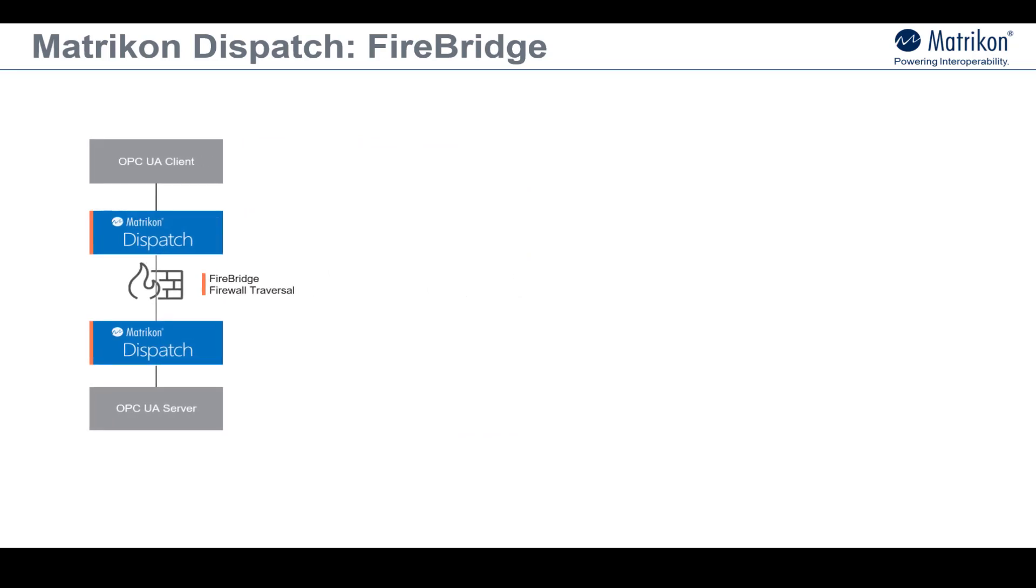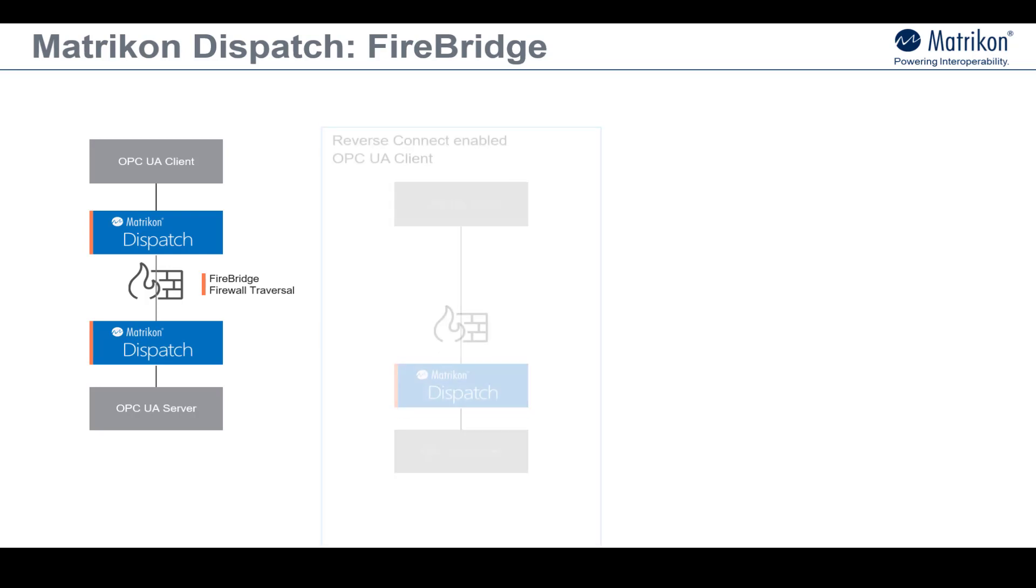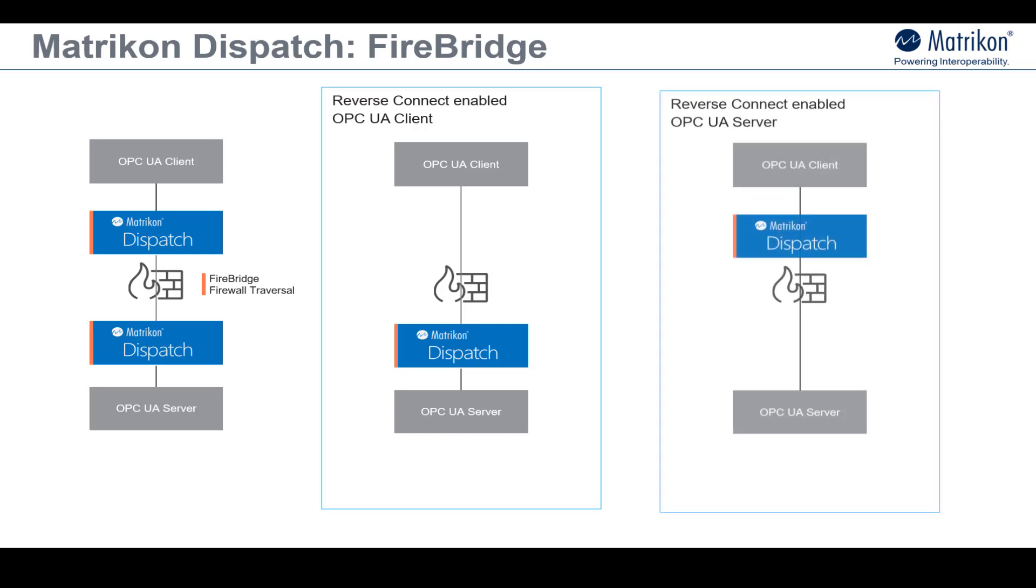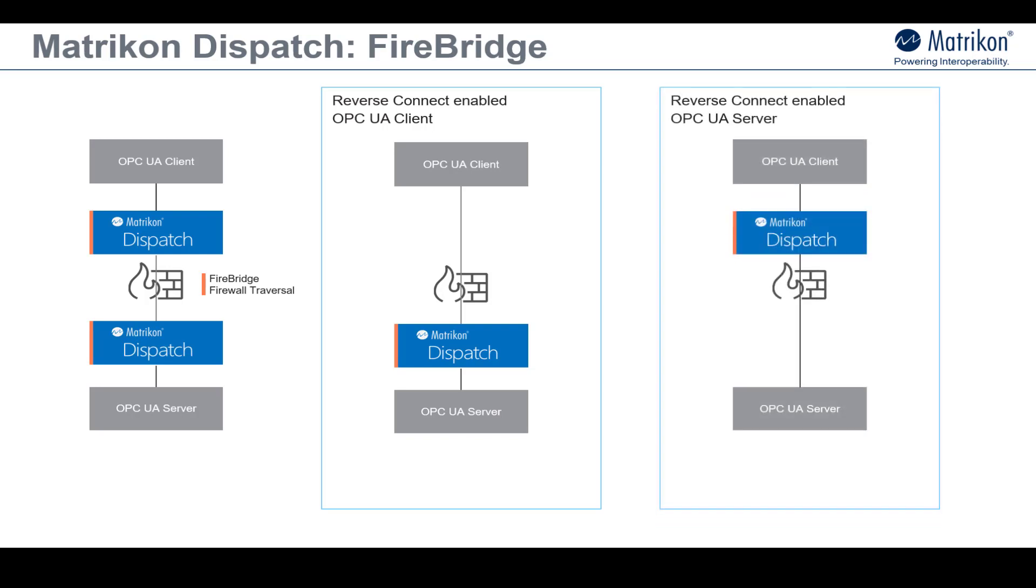As such, Matrikon Dispatch FireBridge technology can be used to facilitate cross-firewall communications on both sides of a firewall in scenarios where neither of your OPC UA clients and servers implement reverse connect functionality. Or, Firebridge can be used to fill in the reverse connect functionality in situations where one of your OPC UA components already supports reverse connect but the other side does not.